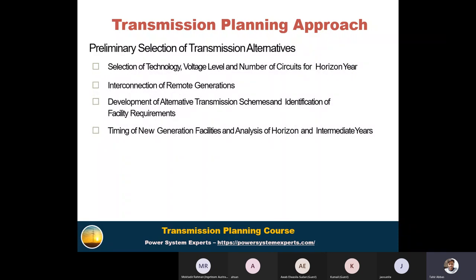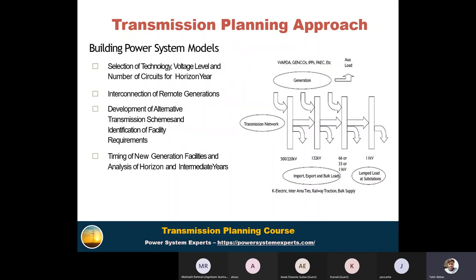Okay, after the horizon is clear and after preliminary selection of transmission alternatives based on the power transfer, based on the conceptual analysis, now we develop a model. After the selection of technology and development of alternatives, you should create a pipeline. Okay, I need a substation based on the demand in 2023, the spot year. I need this grid up to 220 kV. But in the next years, the demand will increase, so I have to augment and extend that substation to 500 kV and 765 kV. So based on the load demand analysis, we basically propose the network.